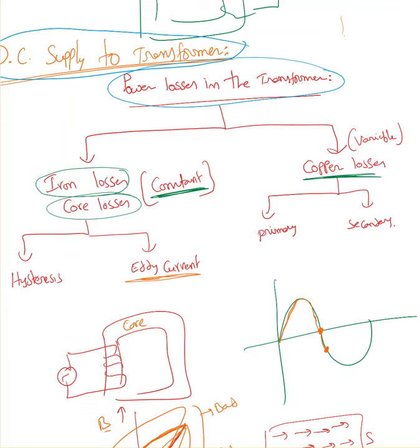The second type is copper losses. These are variable losses based on how much energy you're drawing from the transformer - primary copper losses, secondary copper losses. Wherever you use copper in the transformer, there are copper losses.